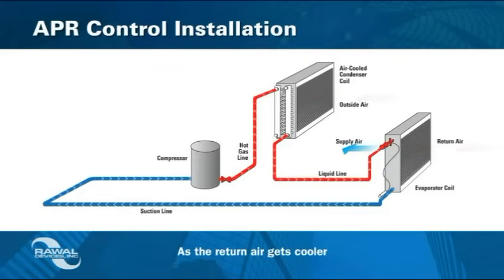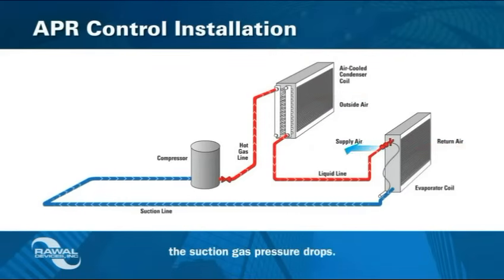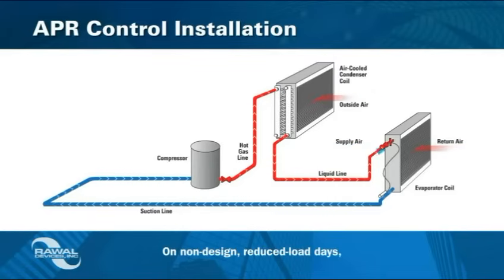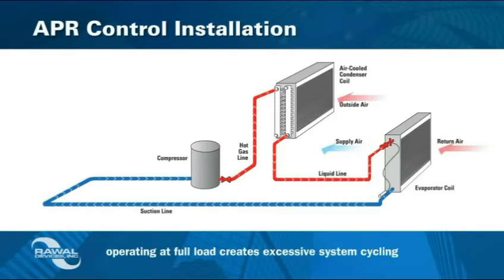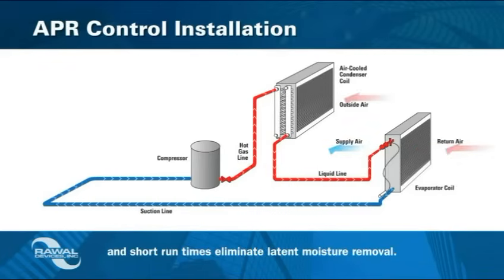As the return air gets cooler, the suction gas pressure drops. On non-design reduced load days, operating at full load creates excessive system cycling, and short run times eliminate latent moisture removal.